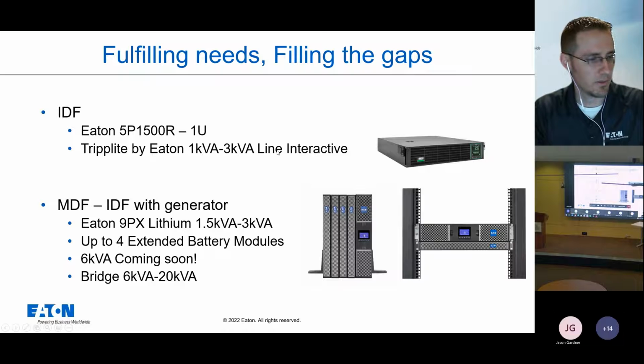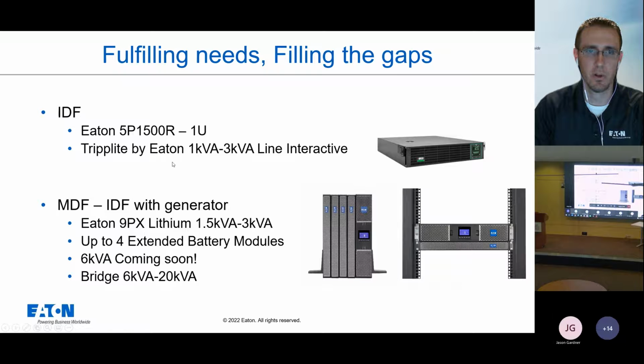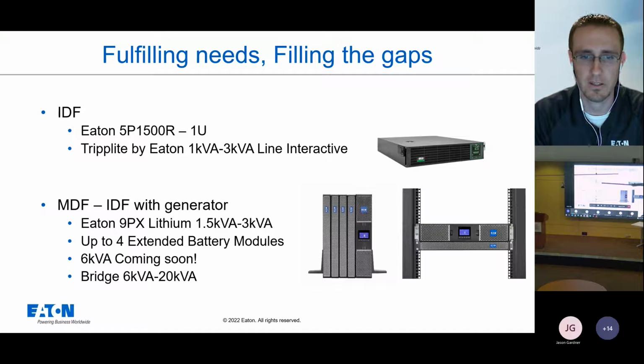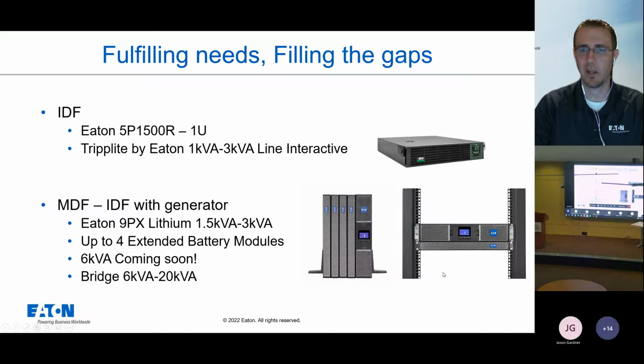So what is Eaton's approach to fulfilling these needs? With the Tripp Lite acquisition, we were able to fulfill IDF in general with 1K to 3 kVA line interactive UPSs, and where space is limited, we have the Eaton 5P 1500 rack unit, which is 1U. For MDF and IDF with generators, we have the double conversion lithium option at 1.5 to 3 kVA with up to 4 extended battery modules. So if you don't have a centralized UPS, or even if you do but still want an hour of runtime on your rack-mounted UPSs as backup to a generator, you can stick up to 4 extended battery modules on these. We're the first to market with double conversion with extended battery modules, though I believe more folks are coming out with these now.